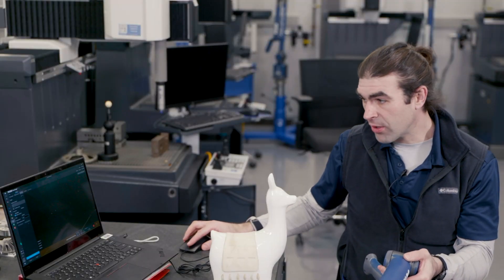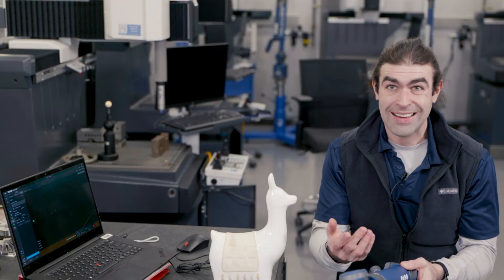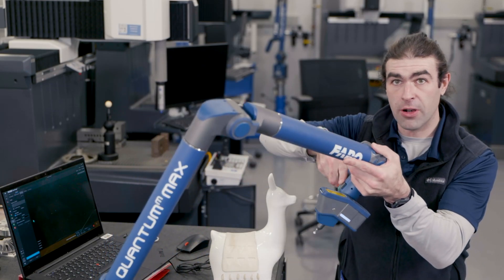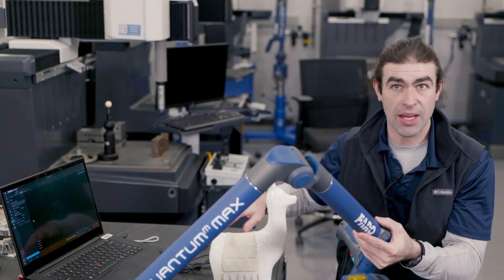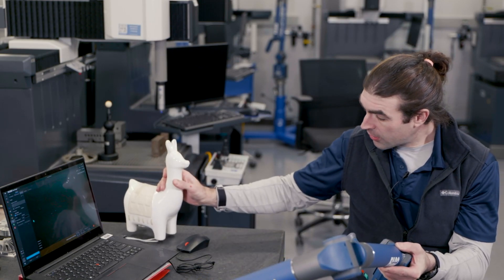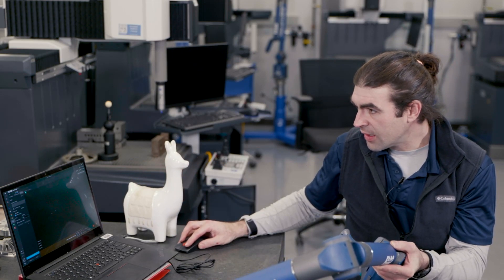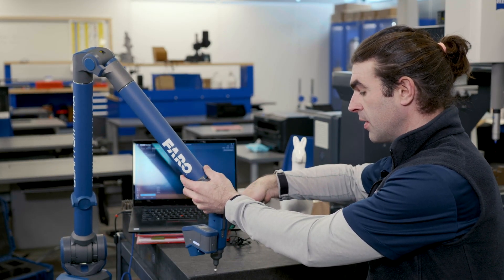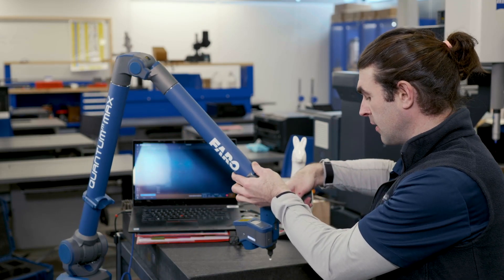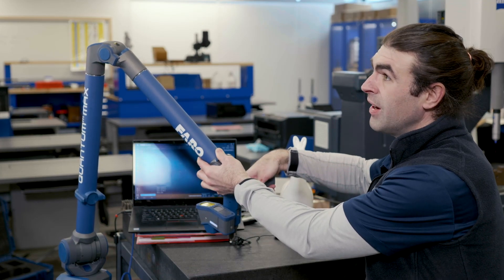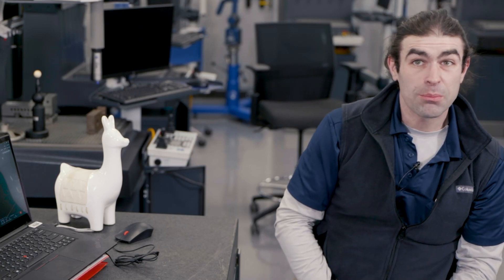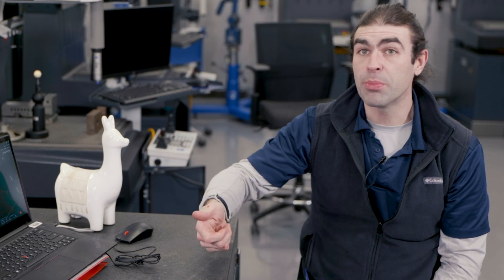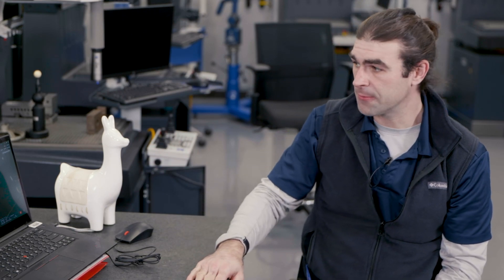So I'm going to go to my software. I'm going to do something called create a clipping plane. If I just scan this part, it's going to pick up everything on the table too, including the table. I might pick up my laptop, my mouse over here. We don't want that to happen. So I'm going to move the part out of the way, and then I'm going to probe my clipping plane. So I just put the probe on the table, pull the green button in a minimum of three places but it could be more, and I'm going to pull the red button when it's above the table. It's important to do that because you want to tell the computer which direction you're working in.